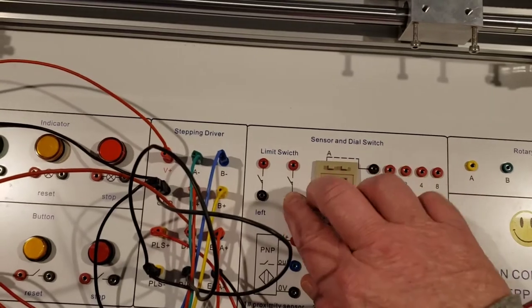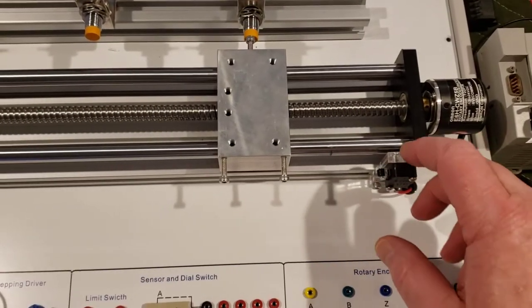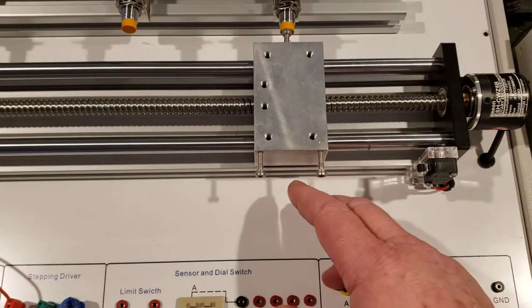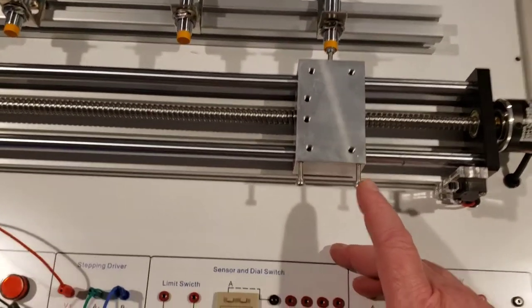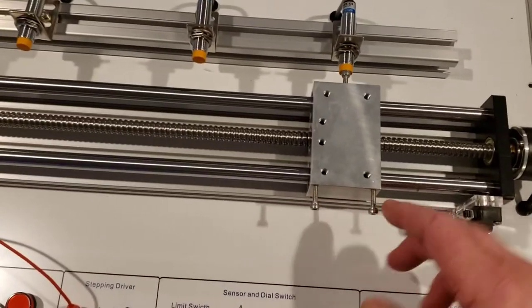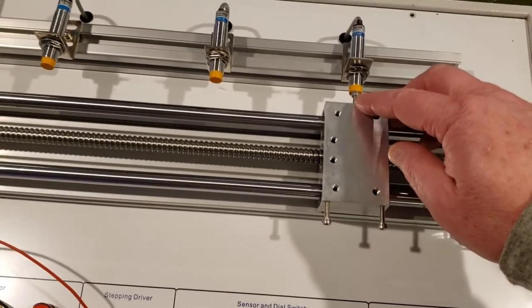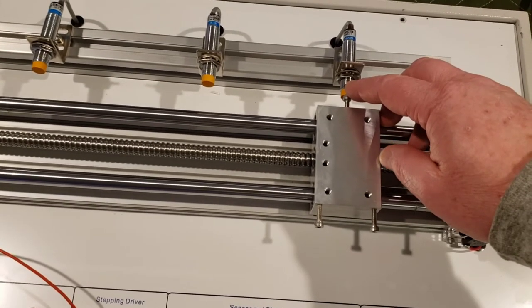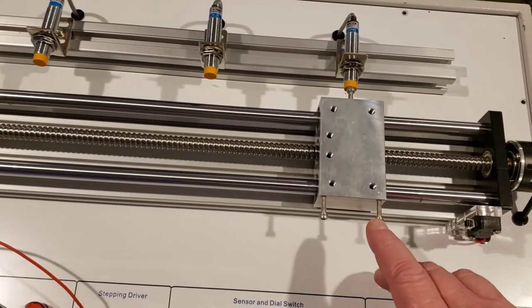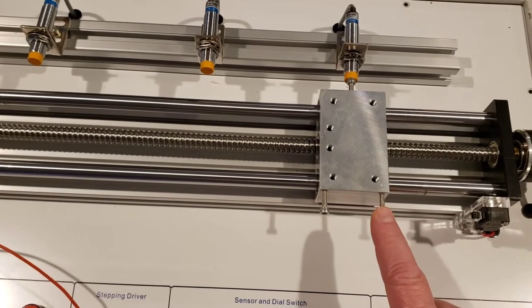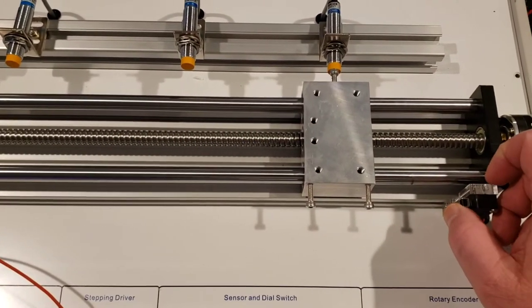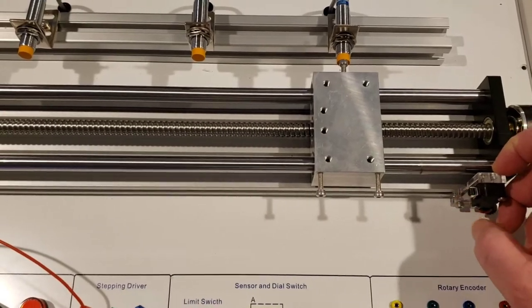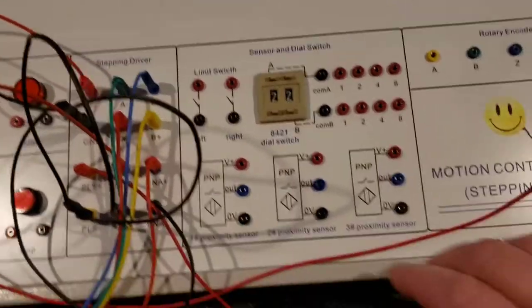These are your two limit switches that are on the end, and they will be flagged off of this bolt sticking out, so it's an over travel. Typically it would stop here on the proximity switch - that's how you'd have it programmed. Then you'll have an over travel coming off of this bolt here, so when it hits the prox it'll drop out the motor. There's different ways that you can do that.